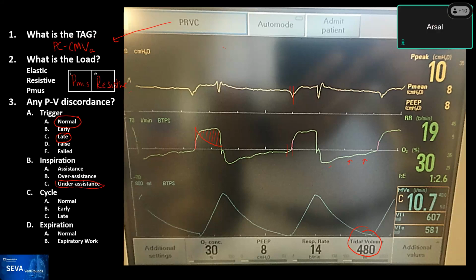Sure. If you look at the waveform, you'll see there's active patient effort going on based on the flow waveform. You look at the pressure waveform, there's a deflection that goes below the baseline, and then it goes up above the baseline as well. That's showing that the patient is working hard, there's under assistance going on.